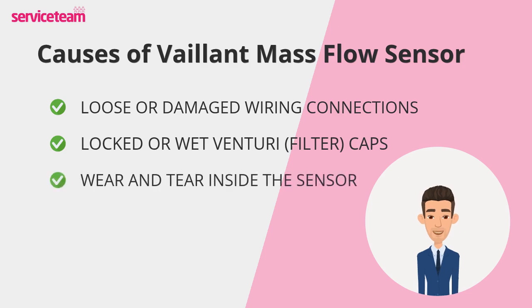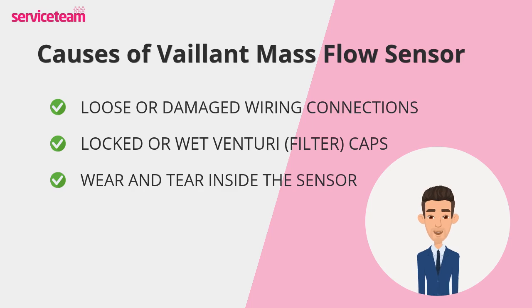Over time, the internal components of the mass flow sensor can degrade or fail. Age-related wear, heat exposure, or continuous operation can prevent the sensor from accurately monitoring gas and air flow. This internal failure can result in poor boiler performance or complete shutdown.